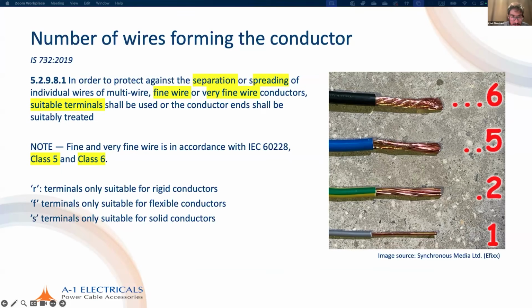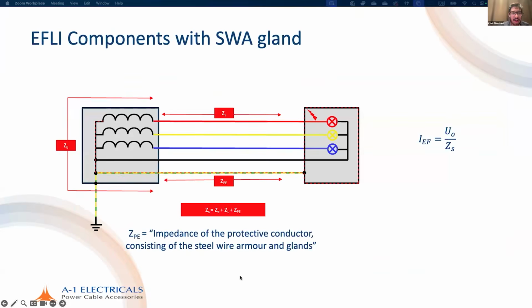Just 1 second. Let's go back to the glands, and there will be one gland here and one gland here. So it is not really star or daisy chain. It is just that there are glands wherever the connectors are, wherever the cable enters an equipment, and the armor has to be utilized for the purposes of a protective conductor. Yeah.